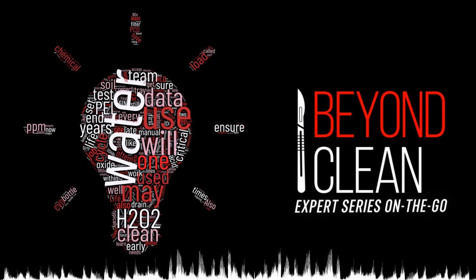Hydrogen peroxide sterilizers start their cycles by removing air from the sterilization chamber to achieve a deep vacuum. The H2O2 solution is then vaporized with heat and introduced inside the sterilization chamber, followed by a waiting period allowing the H2O2 molecules to do their remarkable job. The vacuum within the chamber aids the vaporization of the solution, and the absence of air helps H2O2 molecules to go everywhere. Some sterilizer cycles also include the use of plasma or ozone as a means of further reducing H2O2 residuals and/or to enhance the cycle lethality.